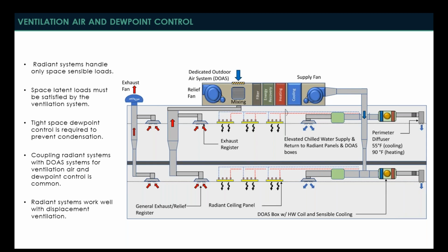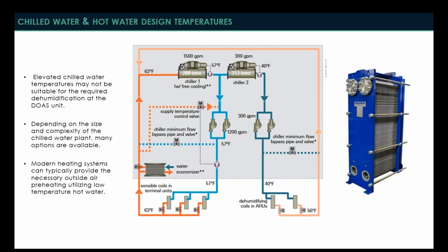Another thing to note is that when we're talking about the ventilation air or the supply air to the space, radiant systems work very, very well with displacement ventilation systems. So a radiant ceiling in combination with underfloor air or a displacement ventilation system, or a radiant slab with wall-mounted displacement ventilation, works very well. So it's something to keep in mind when you're thinking about the air side design for a radiant system.